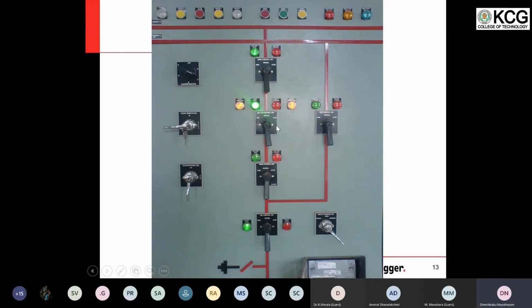Whenever you want to operate the breaker, we use this switch also as an interlock. So when we move on further, like if you are watching a television, you can operate the television either from your remote control, or you can also go in front of the TV and press the button and operate. In the same way, when you are operating the breaker, you can operate either from this panel, or you can also operate from SCADA system. The SCADA system is called as a remote control operation. Somebody operating from remote from a far away location.